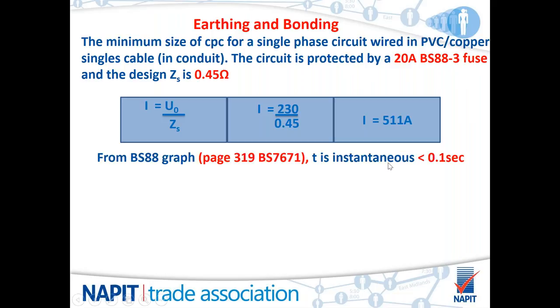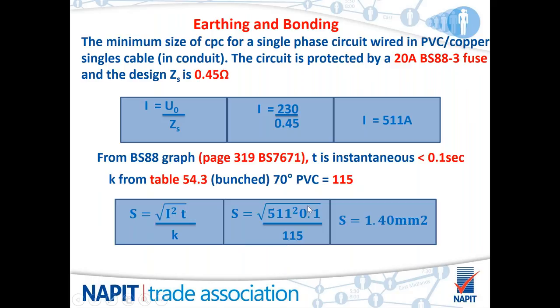If you go to the graphs and choose a 20 amp BS88/3 fuse graph, you would see on page 319 of BS 7671 that the time is actually below the solid line, and therefore it's instantaneous at 0.1 of a second. K, as David mentioned, is taken from the K factor tables in 54, and for a bunched cable, it is usually the figure of 115. All of these go in the adiabatic equation: 511 squared times 0.1, then you square root it, only square root the top bit. When you've got that answer, you divide it by 115, and that equation comes out at a size of 1.40 millimetres squared. And therefore, you need a 1.5 CSA earthing conductor CPC.